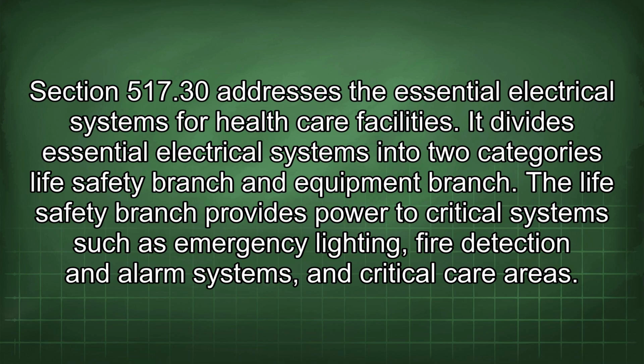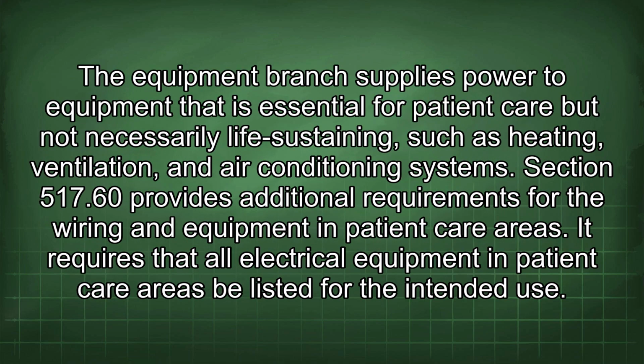It divides essential electrical systems into two categories: life safety branch and equipment branch. The life safety branch provides power to critical systems such as emergency lighting, fire detection and alarm systems, and critical care areas. The equipment branch supplies power to equipment that is essential for patient care but not necessarily life-sustaining, such as heating, ventilation, and air conditioning systems.